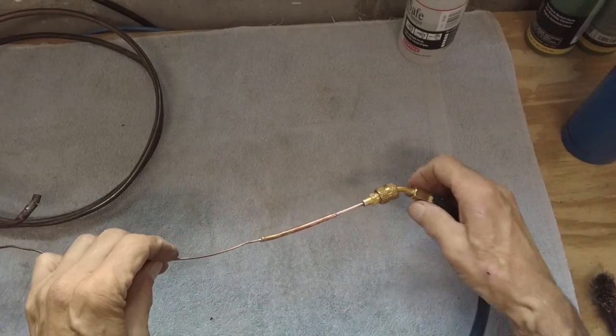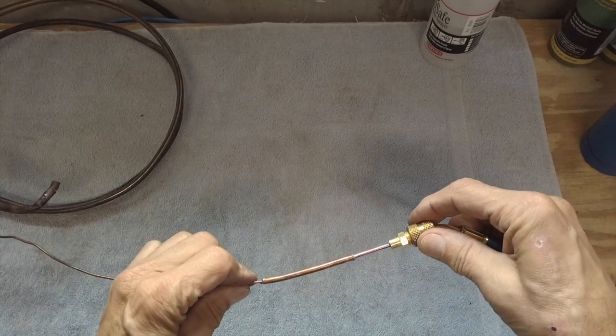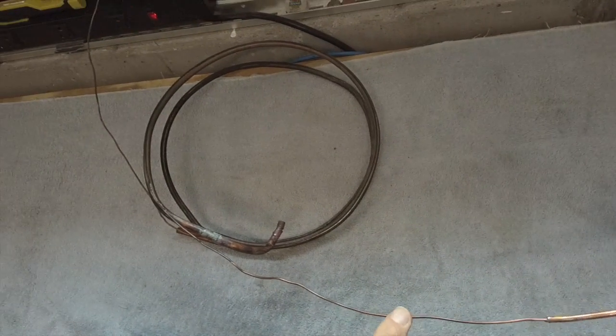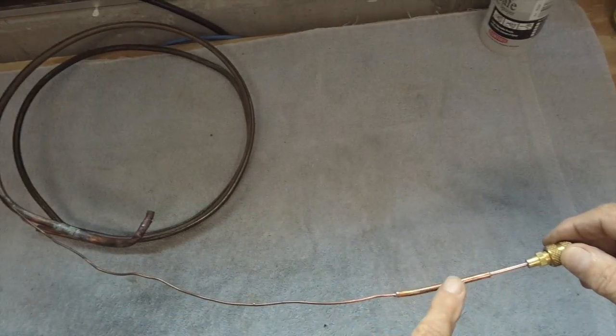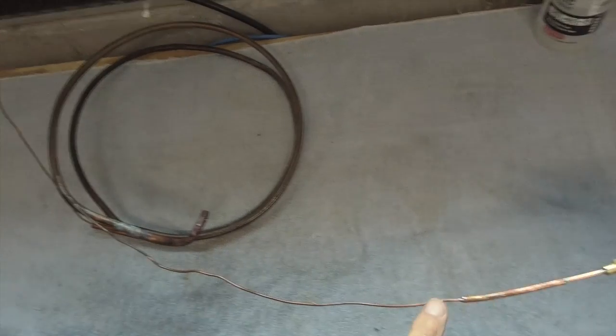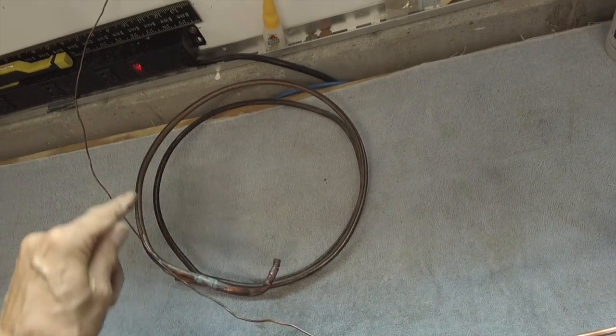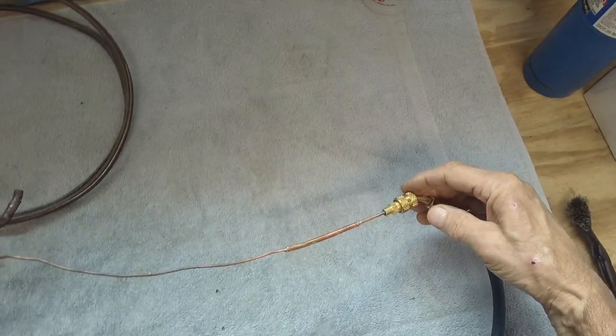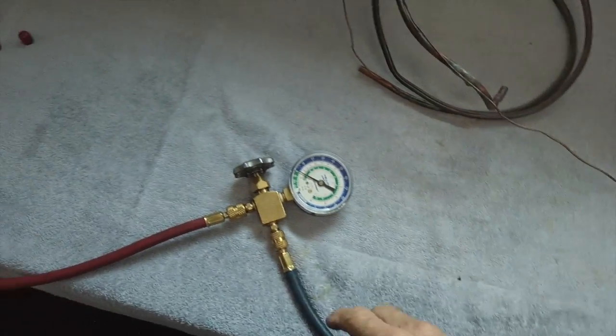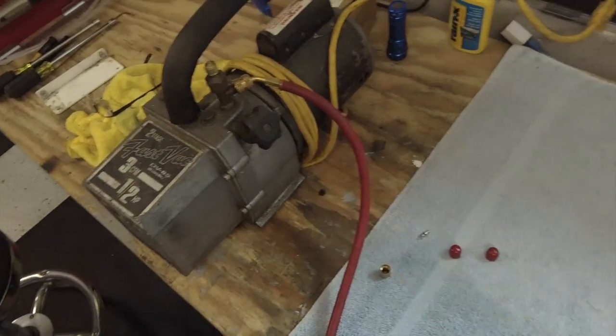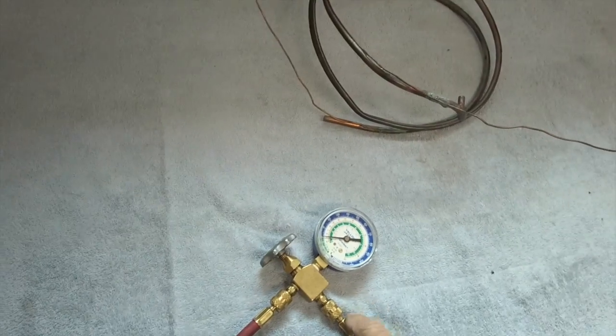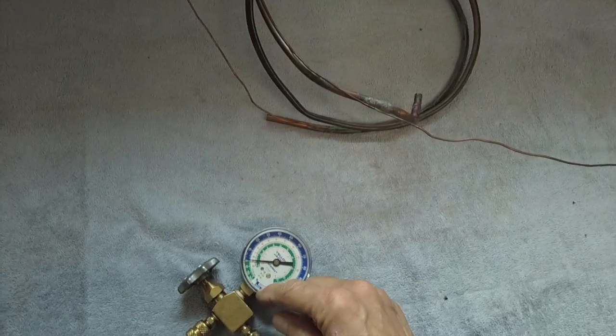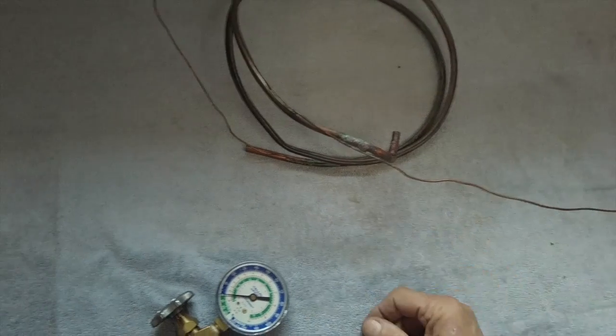So here we soldered our little tool onto the capillary tube, and the flow is going this way from the filter dryer through the heat exchanger, and then out into the evaporator coil. So we've hooked up a vacuum pump, a two-stage vacuum pump. We will pull a vacuum, and we'll be able to see if the vacuum breaks. That means we've cleared this restriction.